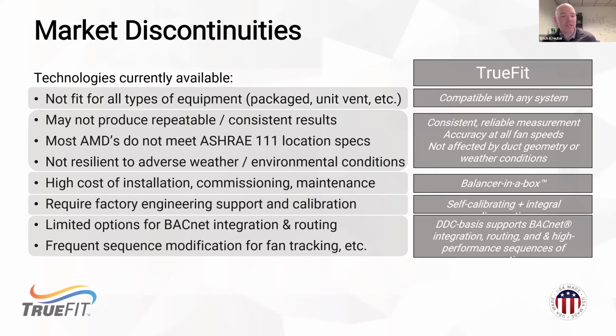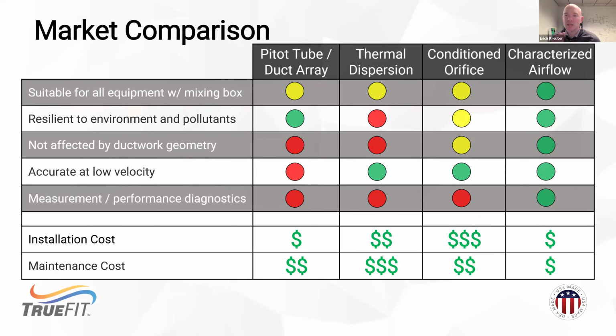So the last slide that I have before we go to questions: different technologies are meant to be applied in different places. In the world of outdoor airflow management, TrueFit really is a great fit for all of these types of systems. The other technologies out there, whether they're orifice plates or thermal dispersion or duct arrays of pitot tubes, all have their place. They all work if they're installed in the proper location and given a chance. The problem is, as an industry, I think we put technology where we have to, not where we're supposed to. And again, that creates a lot of the system inaccuracies and repeatability issues that TrueFit was born to address. So with that, we can grab some questions here.